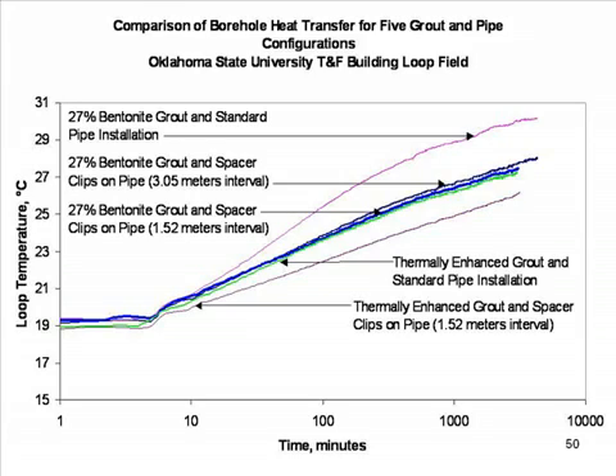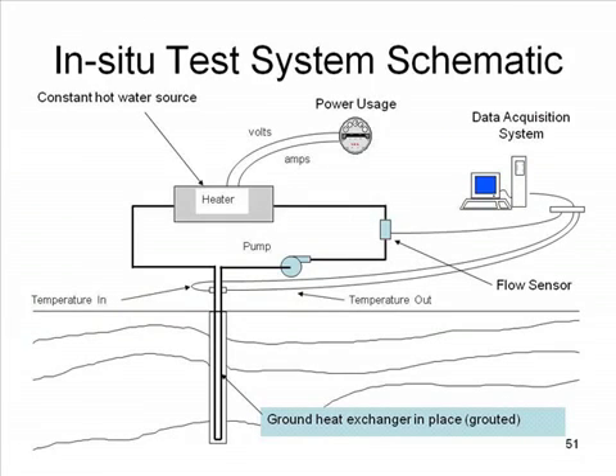And so that's very important, and we'll talk about that in great detail, about the different performance that you can get. The thermal testing, we don't know, and there are various layers in the ground, and so it's important that we know what the thermal performance of the whole borehole is. And here is what we call an in situ test, depends on what part of the country you're from. We take a constant hot water source and a circulator pump, and we circulate that in a ground heat exchanger that's in place and has been grouted. Then we measure the thermal response over time. And that's enough information there to give us what the thermal conductivity is. And we don't care how it changes throughout the borehole. All we want to know is what the value is.